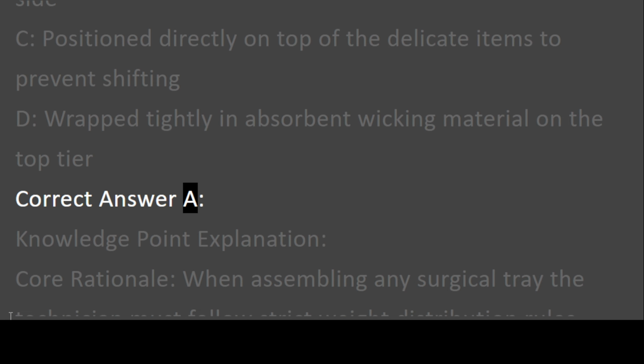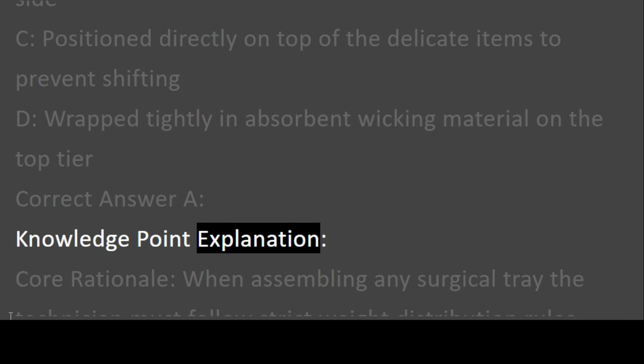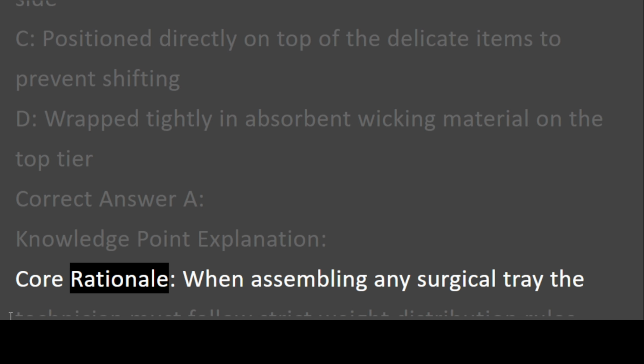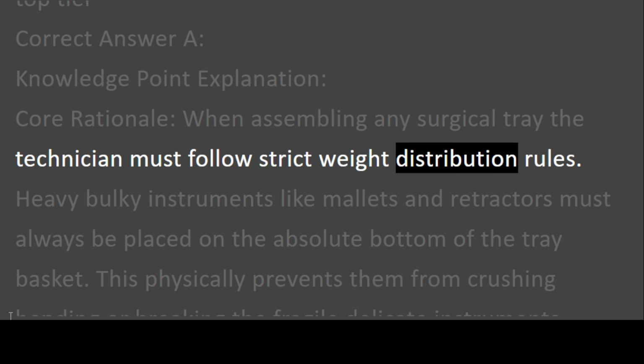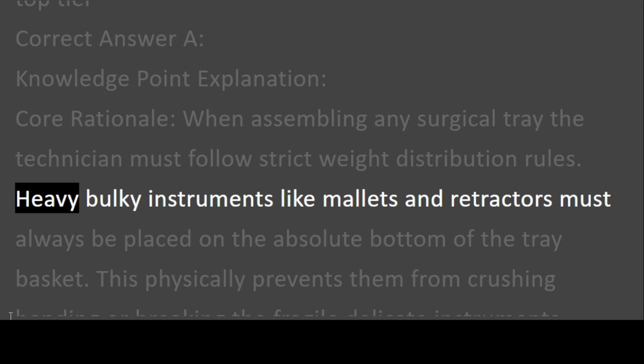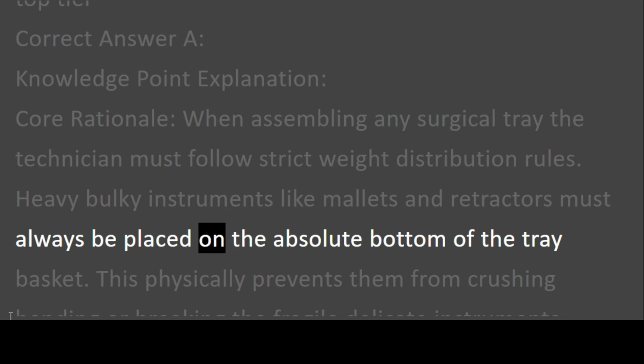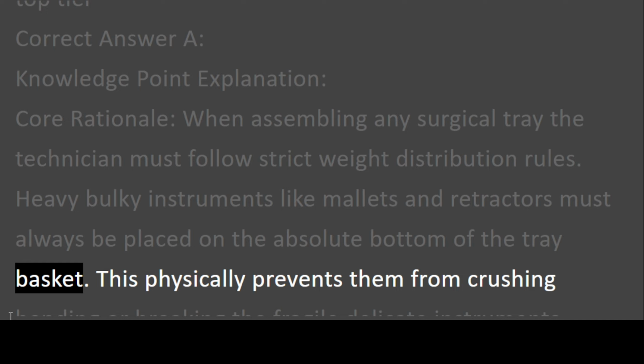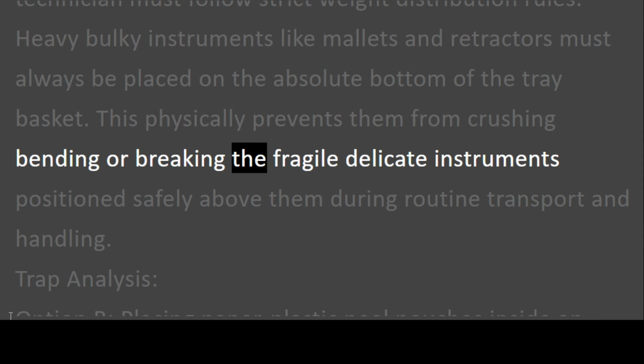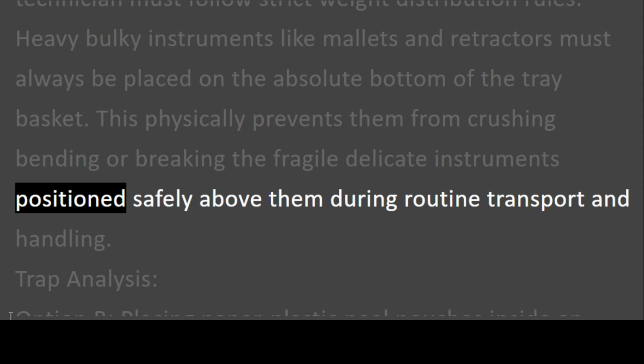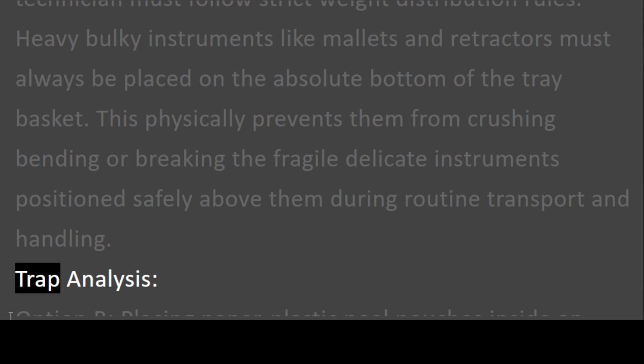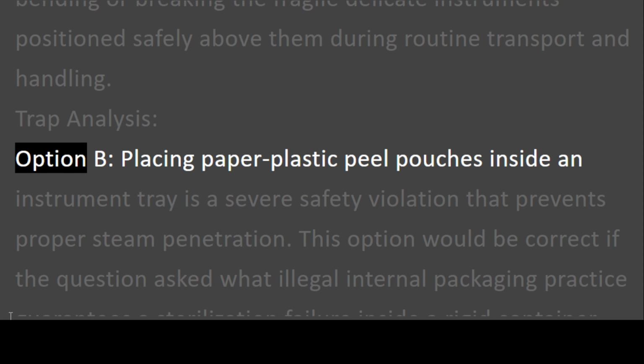Correct answer A. Knowledge point explanation. Core rationale. When assembling any surgical tray, the technician must follow strict weight distribution rules. Heavy bulky instruments like mallets and retractors must always be placed on the absolute bottom of the tray basket. This physically prevents them from crushing, bending, or breaking the fragile delicate instruments positioned safely above them during routine transport and handling. Trap analysis. Option B.